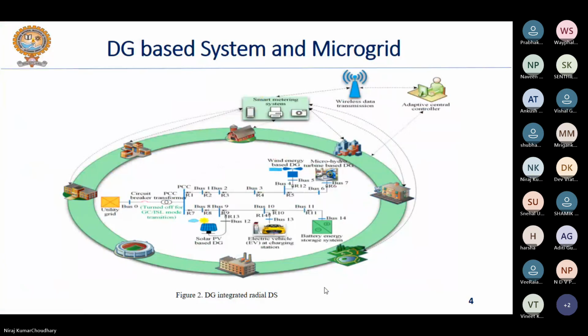Okay. So now here in this figure two, you can see a DG based system and the microgrid. Earlier, I was saying that all the distributed generation based power systems are not classified as a microgrid because there are certain features that must be fulfilled before it is called a microgrid system. One of the main key features is the ability of a microgrid to operate in both modes of operation, that is, the grid connected mode and the islanded mode of operation.